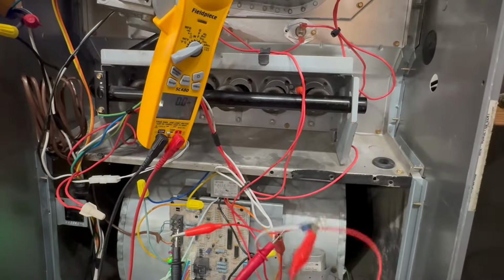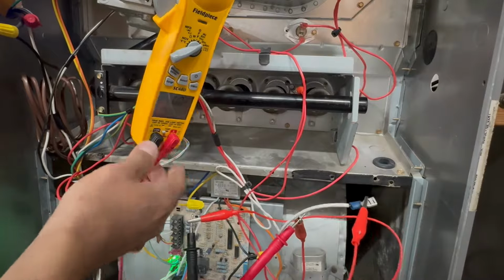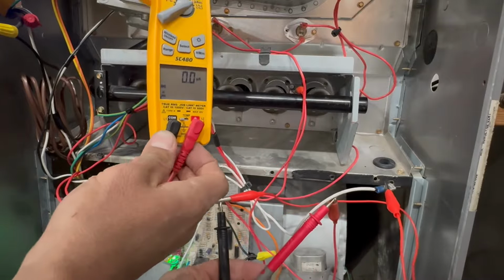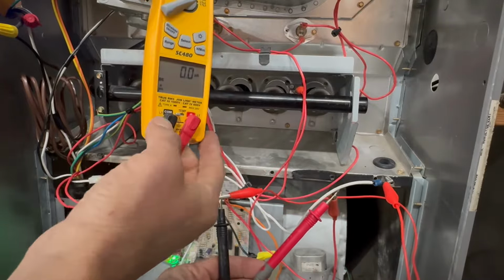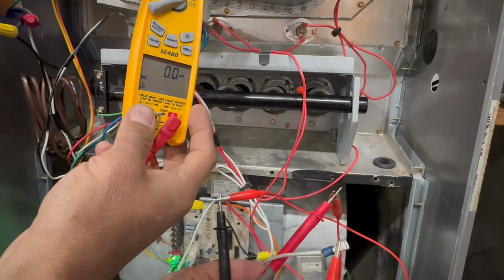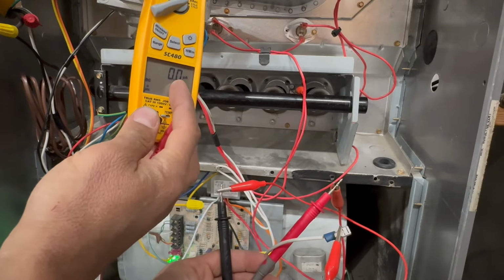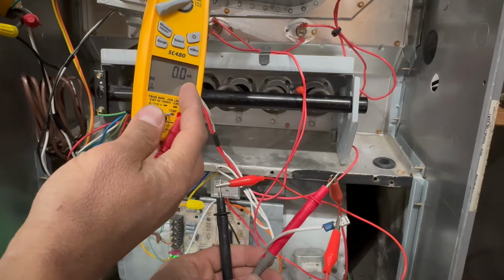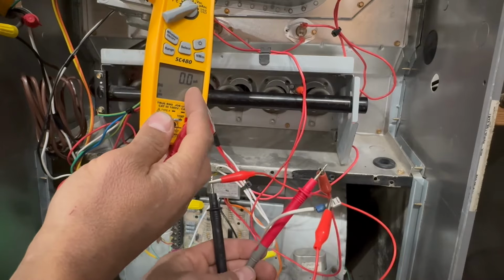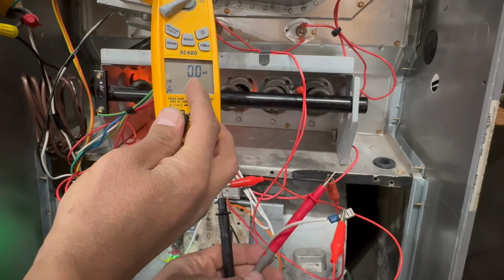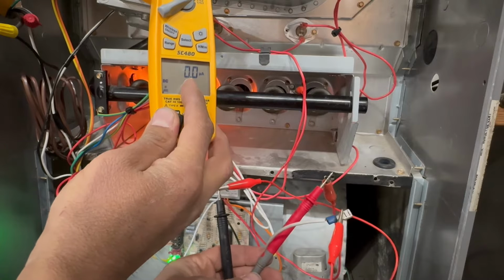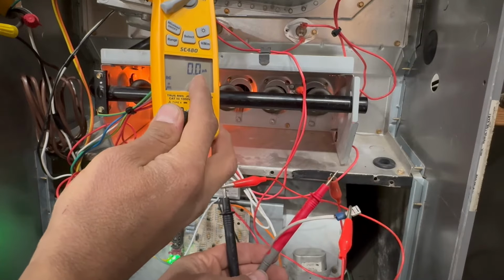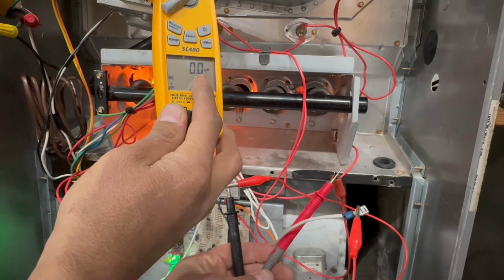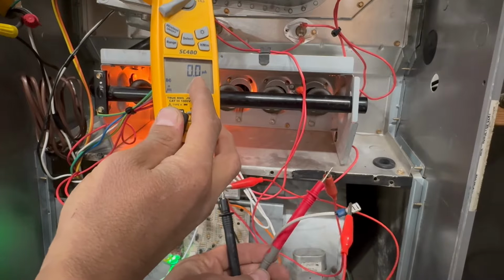So I have my leads here, right? But I want you to look at that right there. Look at my microamps. You have to have it on microamps. Manufacturers will say 4 to 6, some will say 3 to 6. A good rule of thumb would be 3 to 6 microamps. So keep an eye on that right here. Just keep an eye on that. And look, we're going to get microamps.